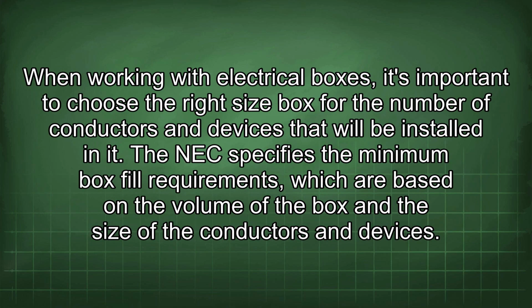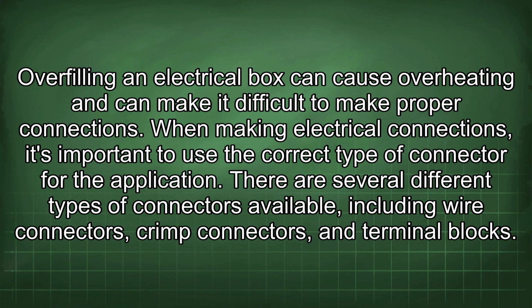When working with electrical boxes, it's important to choose the right size box for the number of conductors and devices that will be installed in it. The NEC specifies the minimum box fill requirements, which are based on the volume of the box and the size of the conductors and devices. Overfilling an electrical box can cause overheating and can make it difficult to make proper connections.